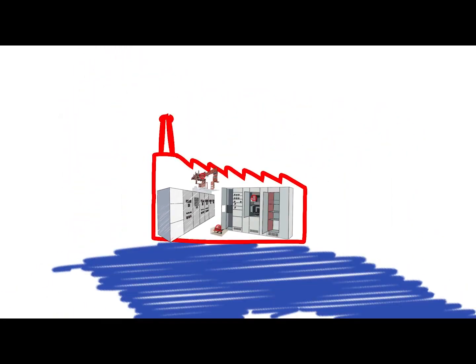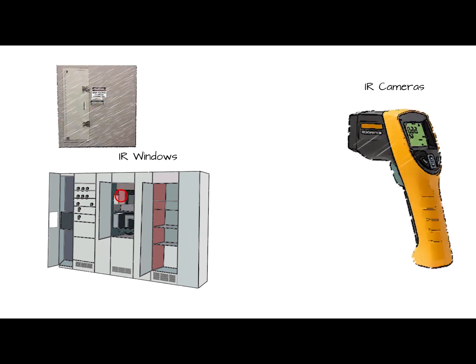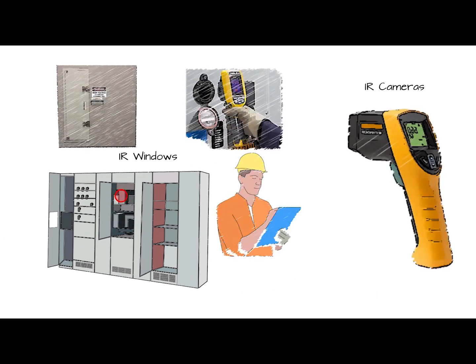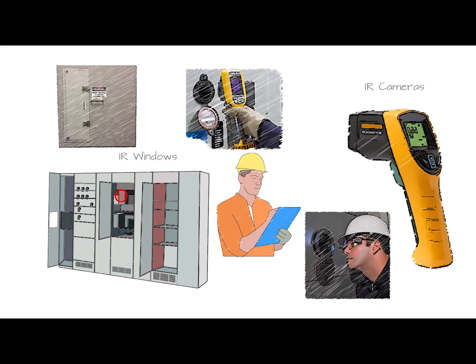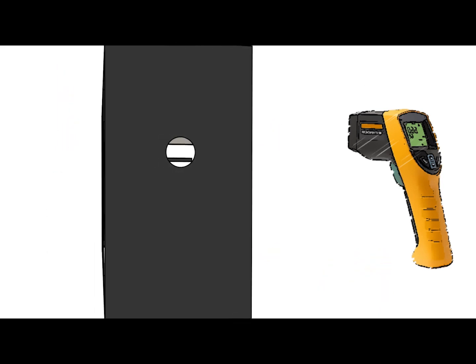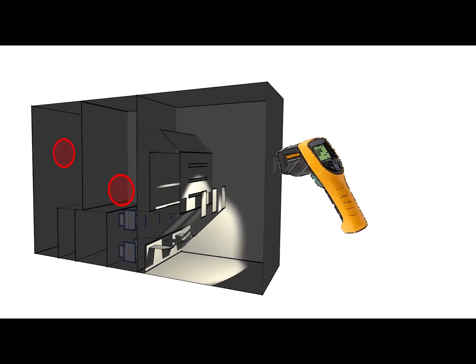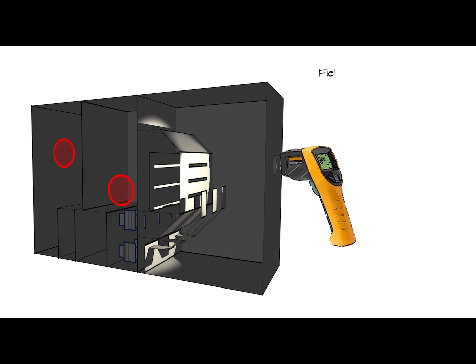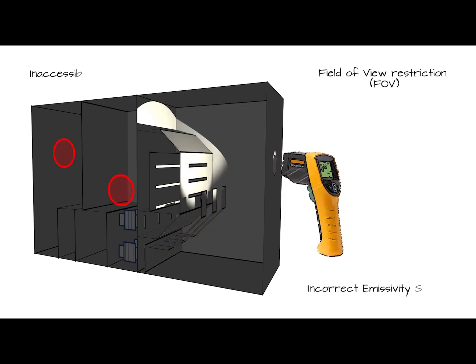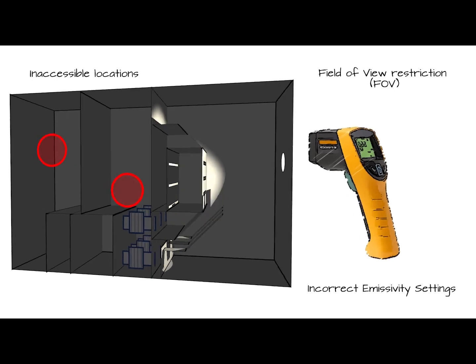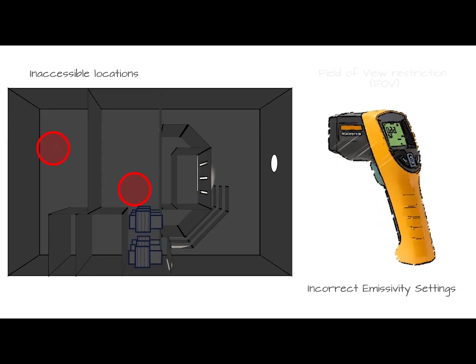To overcome these shortfalls and to measure the temperature of the live conductors, some facilities use infrared cameras and windows. With this method, an IR camera is directed at a live conductor either directly or through an IR window to measure the rise in temperature.